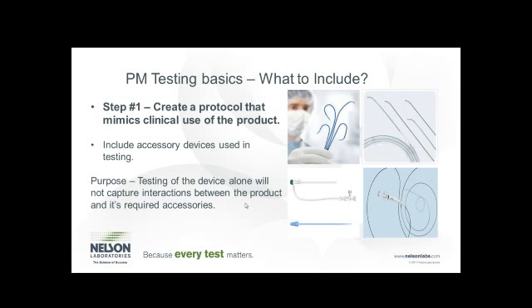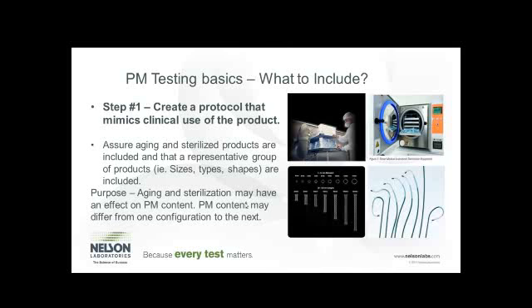We recommend to our customers to design a model or to choose a model based on the anatomical vasculature that their device will be most typically exposed to. We also recommend, as does the FDA and other guidance documents, to include accessory devices used in testing. The purpose for this is to determine if additional particulate may be generated from exposure of your device to the other accessory devices used clinically. Usually a control is performed prior to use of these accessory devices to make sure that they're clean and not contributing significantly to your count. We have had several occasions where clients decided not to use them and had their submission kicked back because of non-inclusion of those accessory devices.